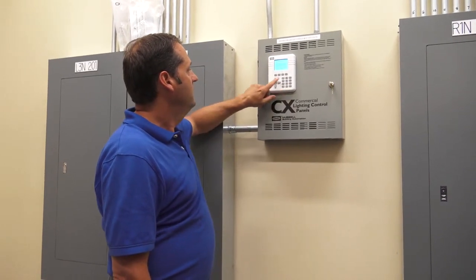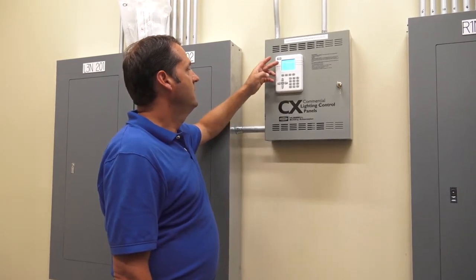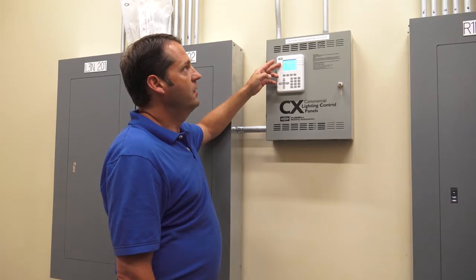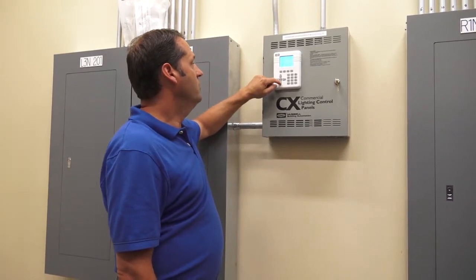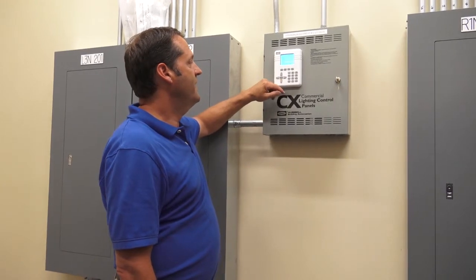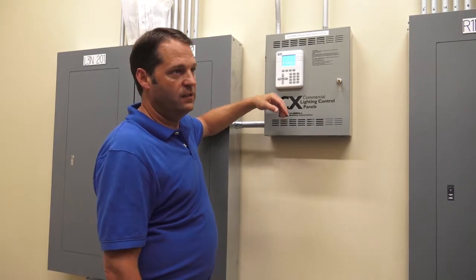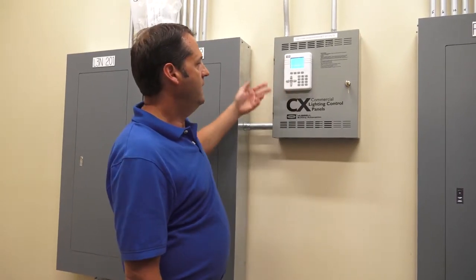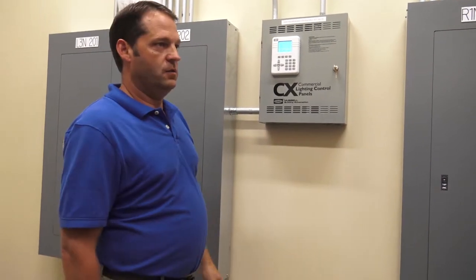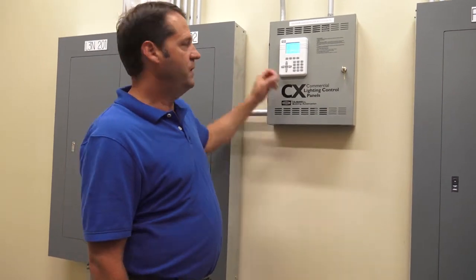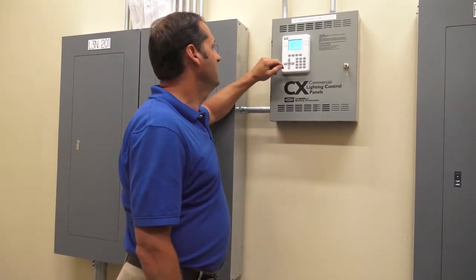Okay. System status. That's when you can look to see if your relays are closed or open. What your groups are doing, what your inputs are doing. This is more diagnostic type things. If you're having an issue or if you're doing a remodel and you need to figure out, okay, I got a set of low voltage wires coming in here. Which switch do those go to? Well, you can have somebody operating the switch. You'll see the little light up that says, okay, that's the switch in the main hallway.